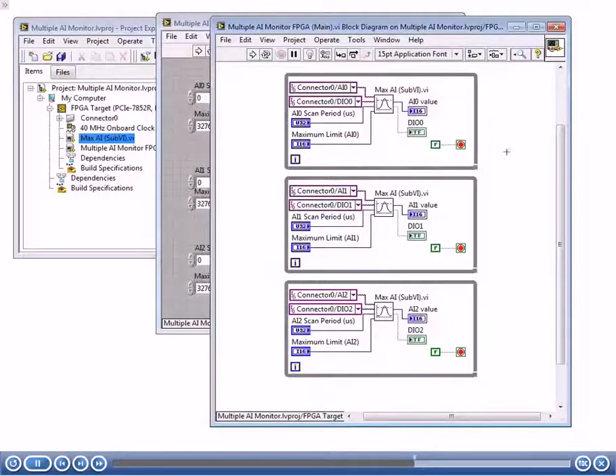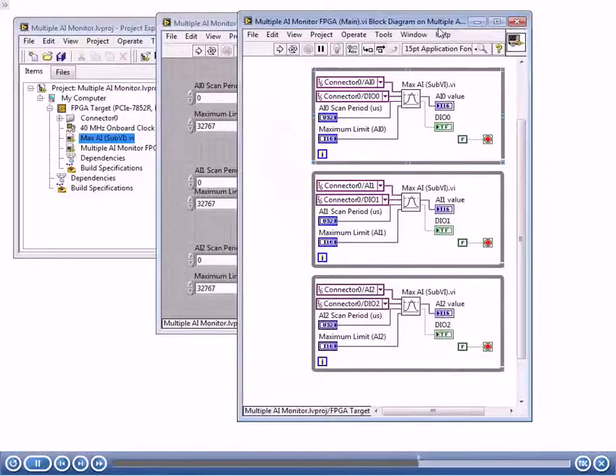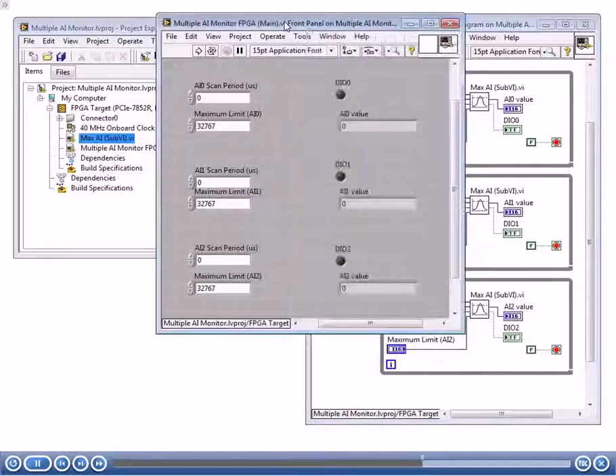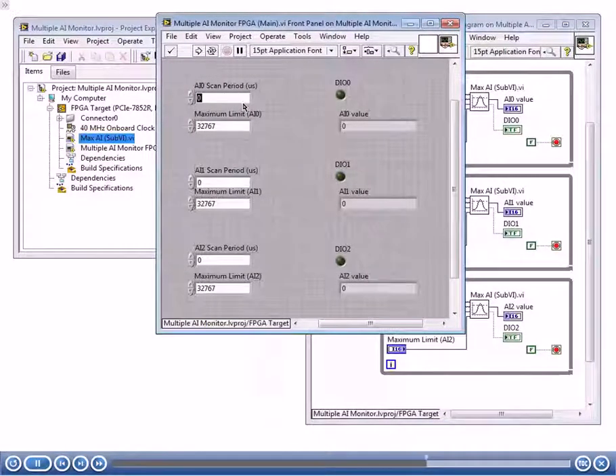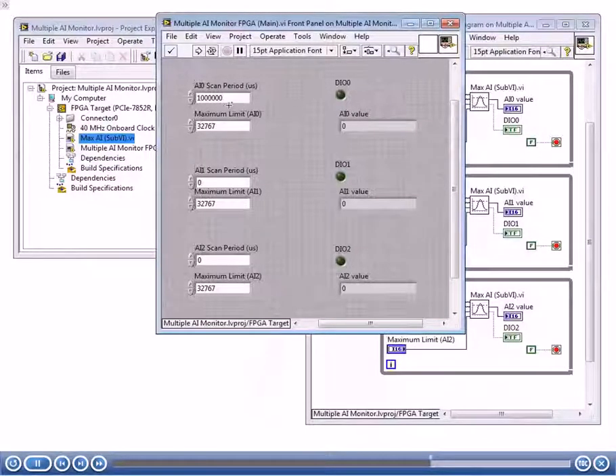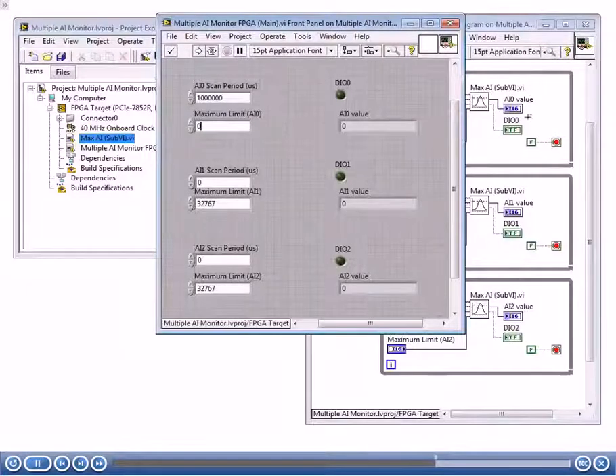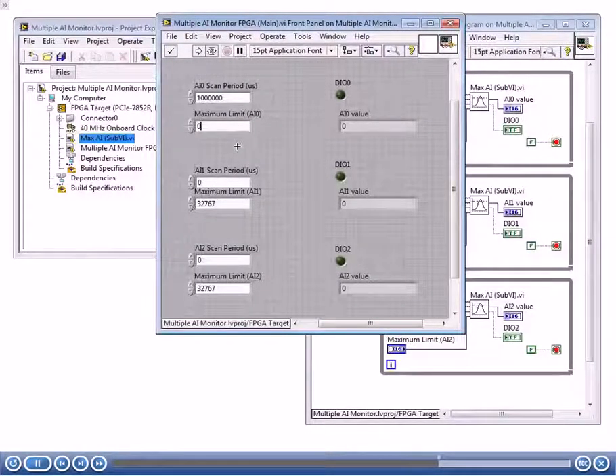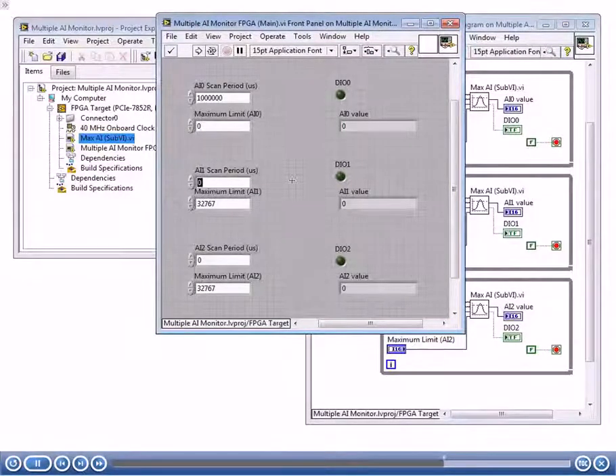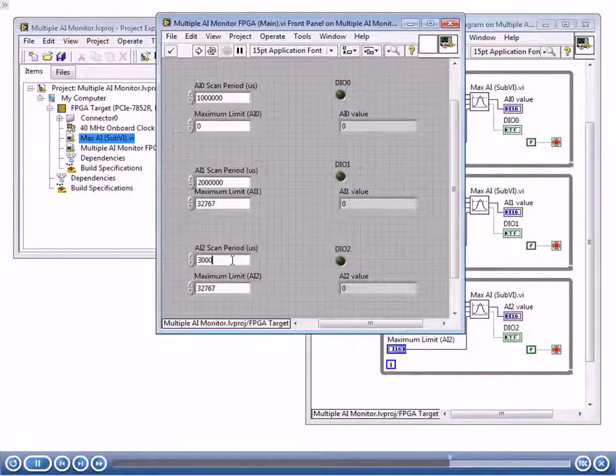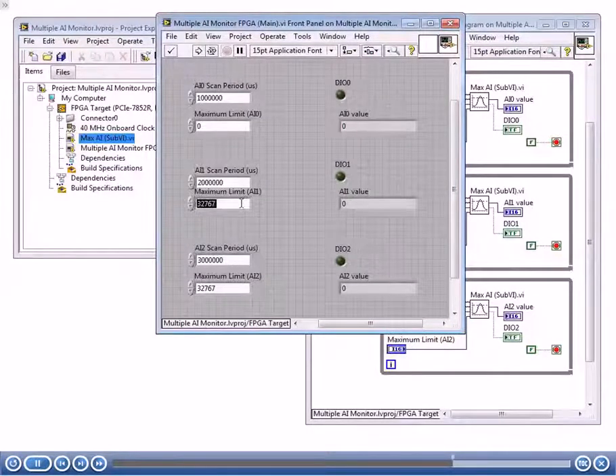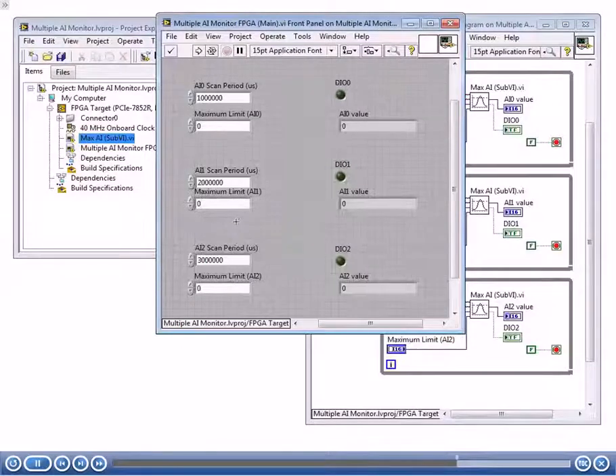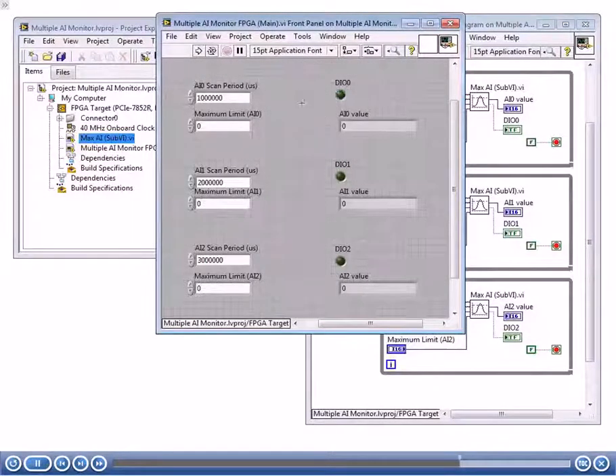Before we do any compiling, of course, we want to make sure everything is working in our simulated environment, because here we have our debugging tools and all that. Let's go ahead and run this. I'm going to put a scan period here. Notice that it's in microseconds. I'm going to make this one second, and I'm going to put a maximum limit of zero. Because this is an I-16, it's going to go from about negative 32,000 all the way up to positive 32,000 something. Here I'm going to make this one two seconds, and I'm going to make this one three seconds. I'm going to make the maximum limit zero here and the maximum limit here. So in this simulation, about half the time, it'll cross the threshold.